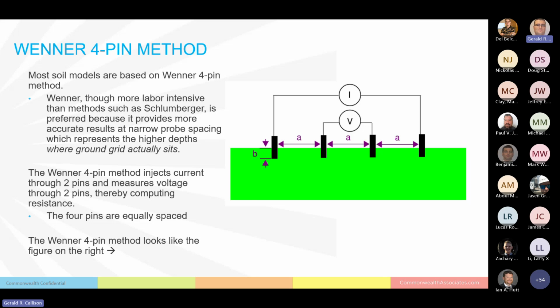If you think about it, your ground grid is typically sitting 1.5 to 2 feet below the surface of the finished earth. That's going to have a tremendous impact on the performance of your grid. Yes, lower layers will as well, but the accuracy of those upper layers is very critical to predicting the performance of your ground grid, which is why we need that more labor-intensive Wenner 4-pin test.